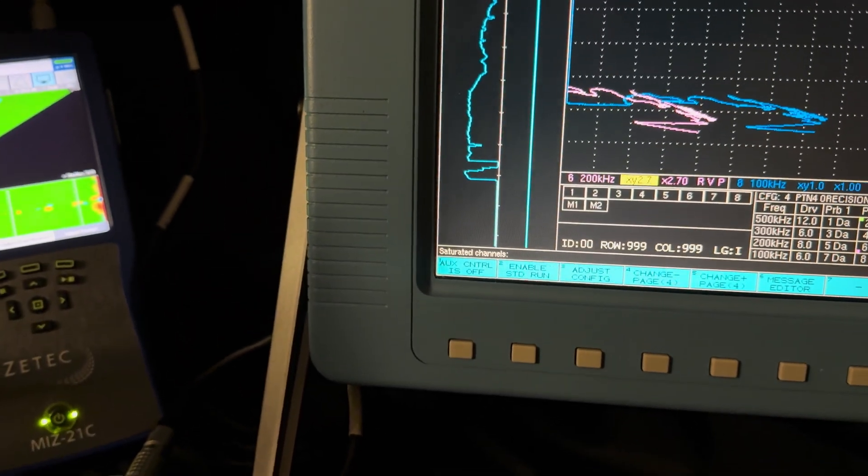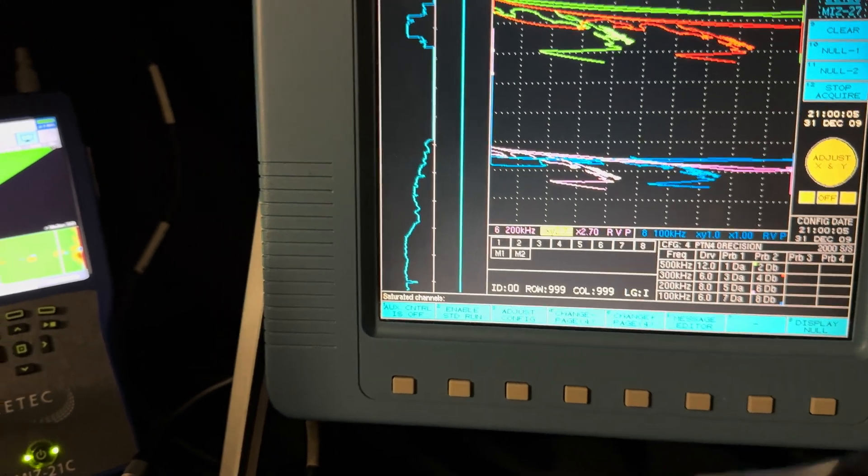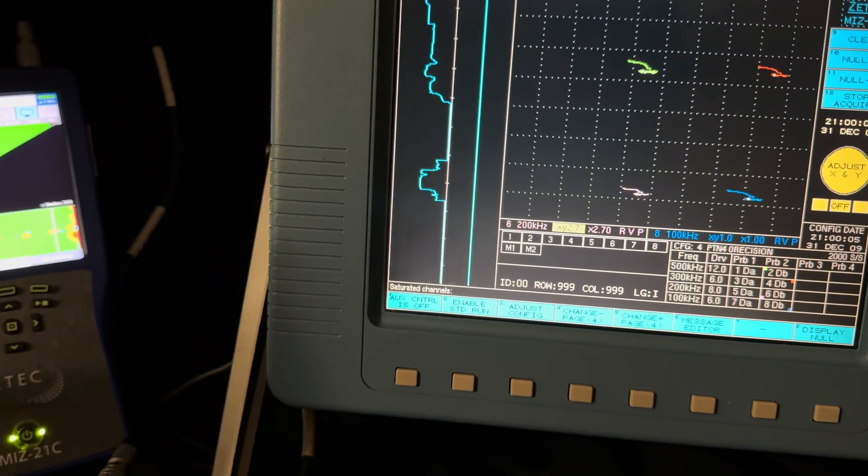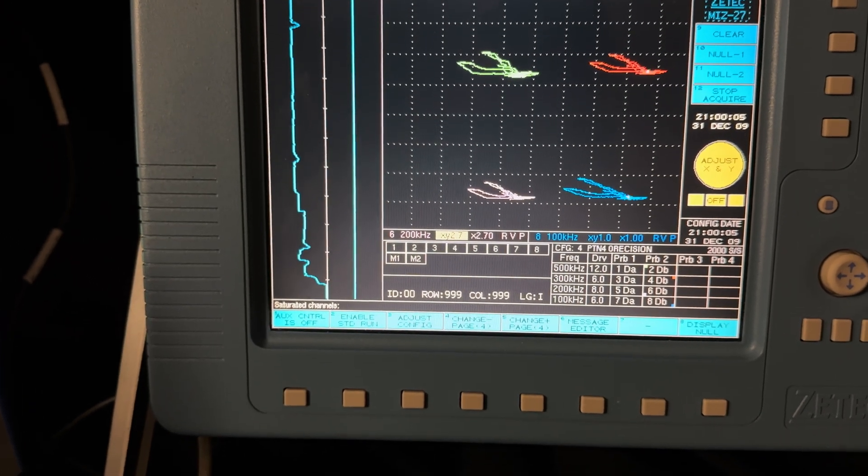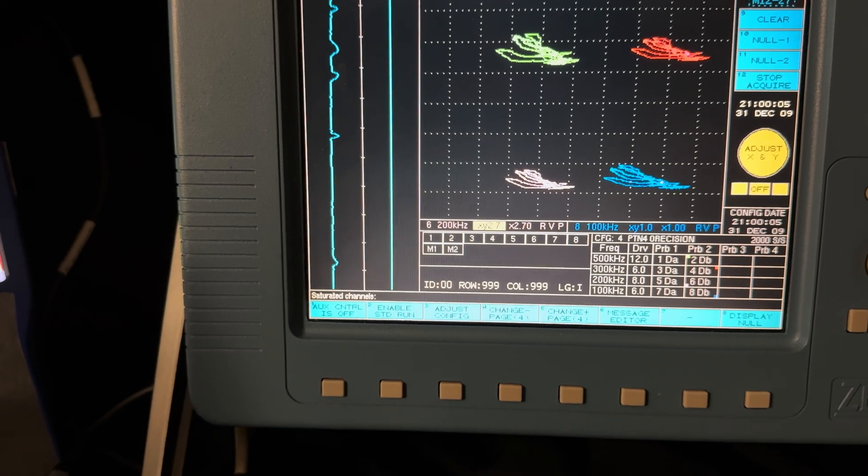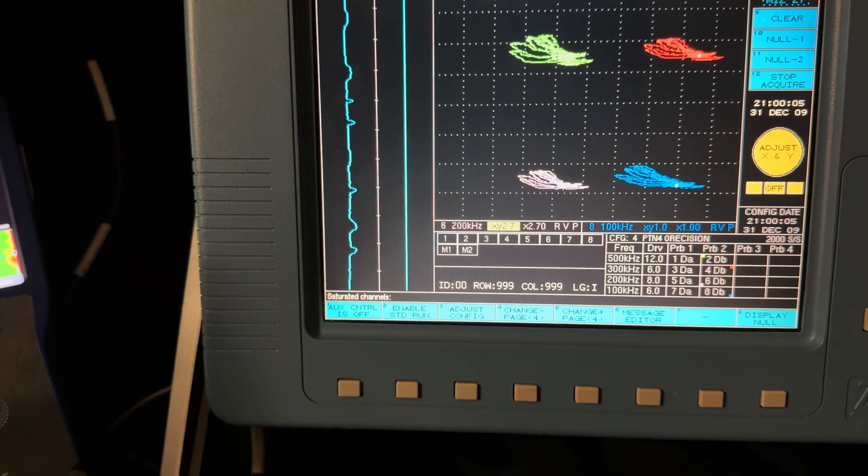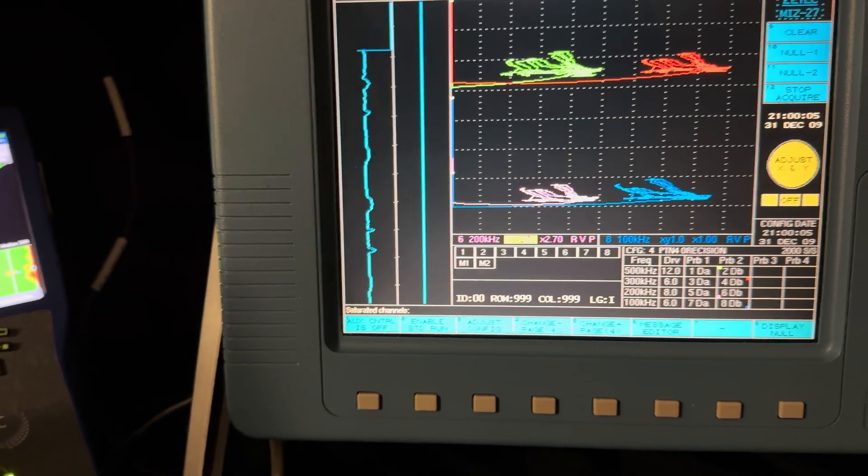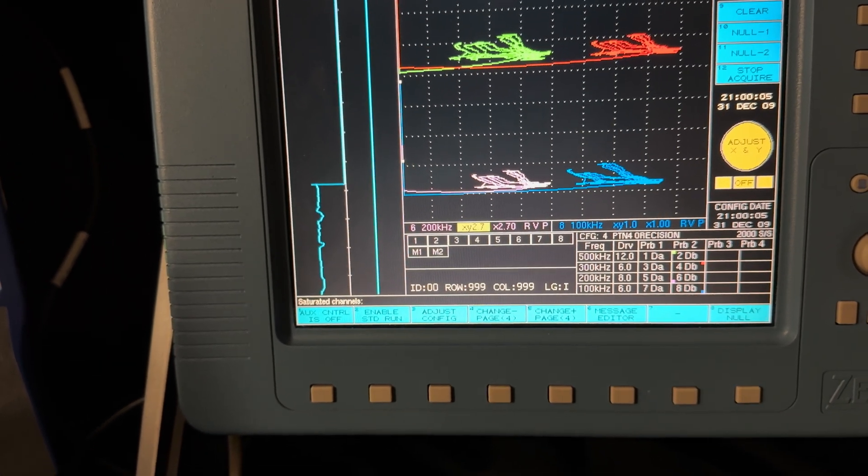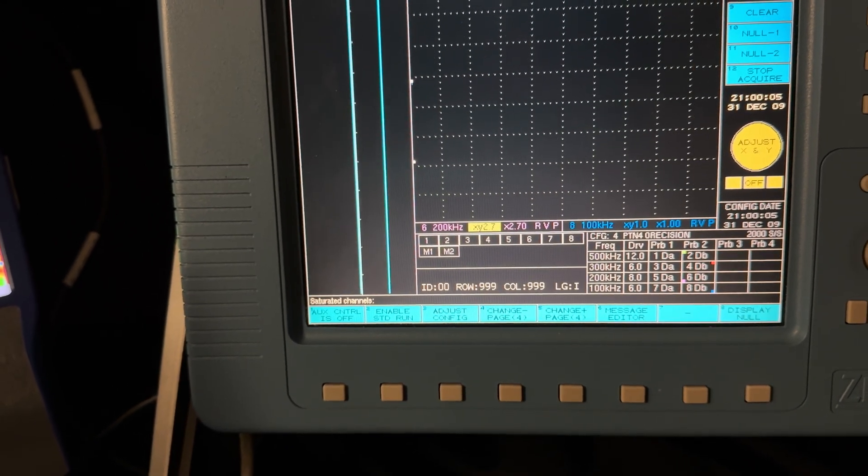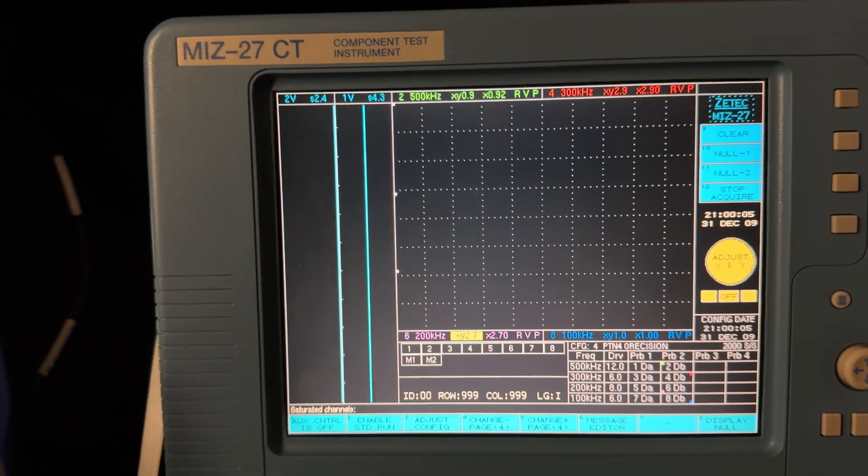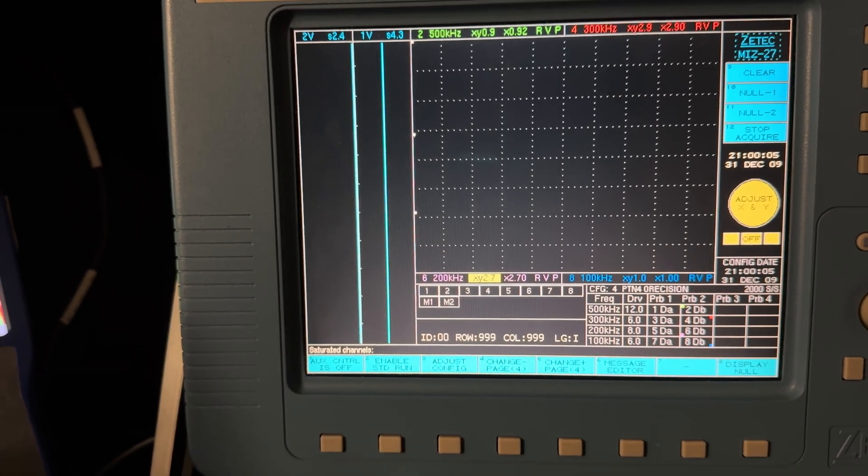Now you may be asking yourself, what's the value in multi-frequency testing for doing this type of scan? And it's a good question. And the truth is, not much. You know, this isn't tubing inspection. Tubing inspection is one of those inspections where the use of multi frequencies is very powerful because it helps you determine what signals are relevant and what signals are nothing but troublesome noise.